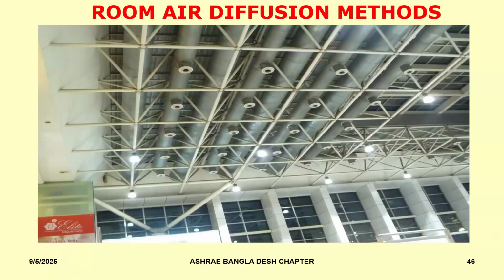The other issue in this particular application is you can see that there are these ducts which are carrying the supply air, and that is directly blasting the air downwards. And you could see these ducts which are alternate. You don't see any grills or anything here. Why is that? That's because that's supposed to be the return.